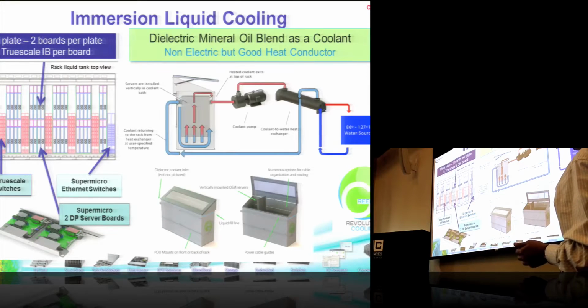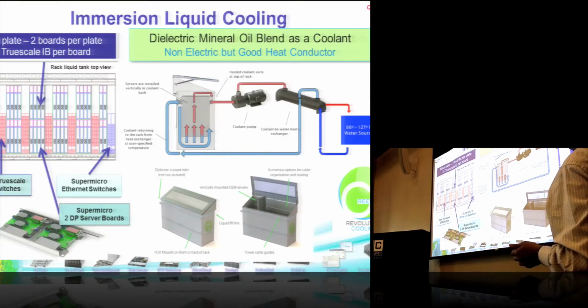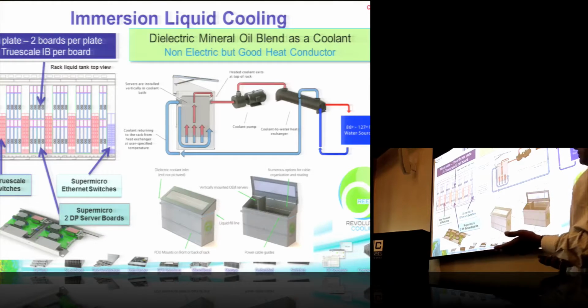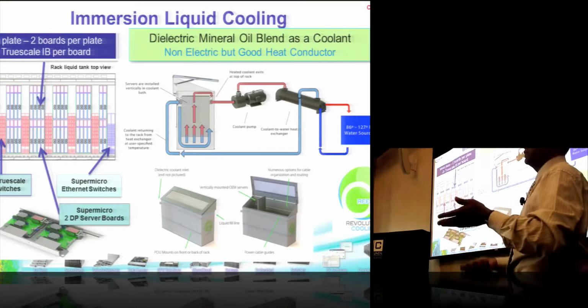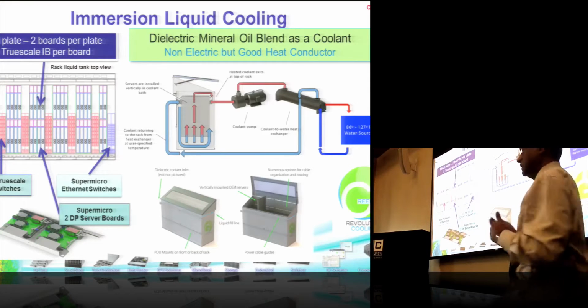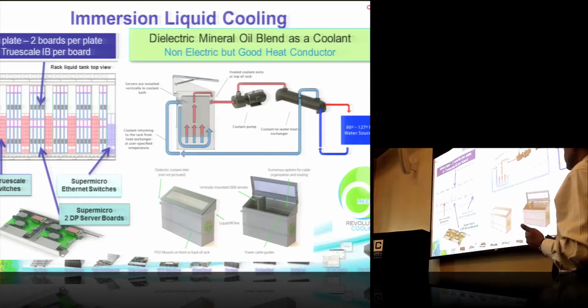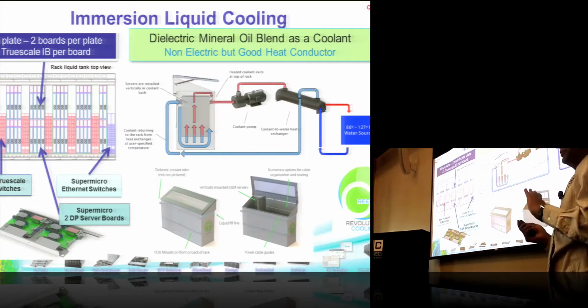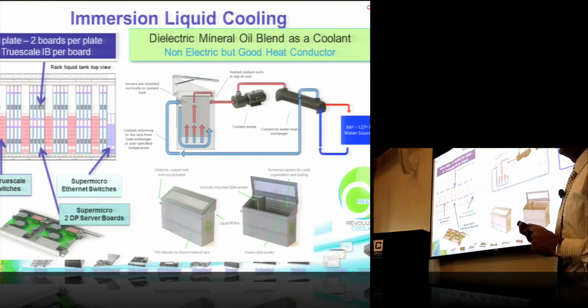There's a dielectric liquid in the tub, and then a pump that pumps in and circulates the liquid, and you also have heat exchange through the chilled water. This is basically your existing infrastructure, and this is your new stuff. So again, from a data center perspective, if you do have racks installed, you've got to go replace it, but from an OpEx, CapEx perspective, this is probably your best bet in terms of cooling.